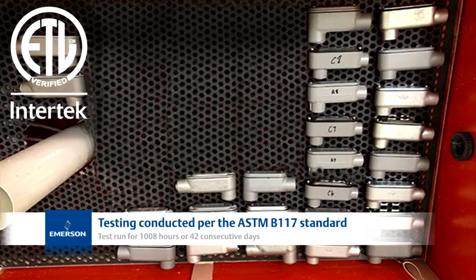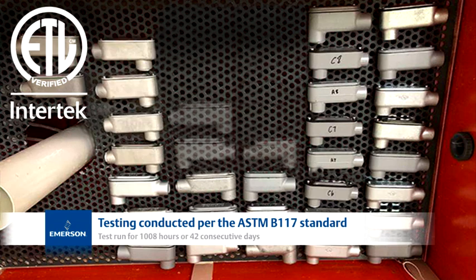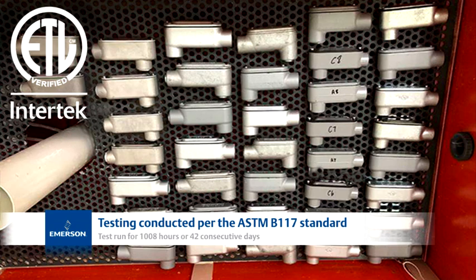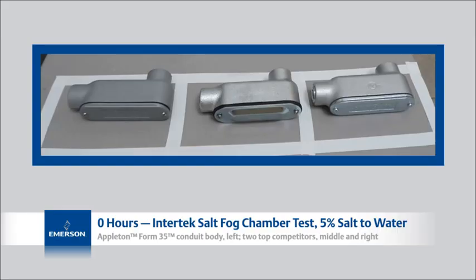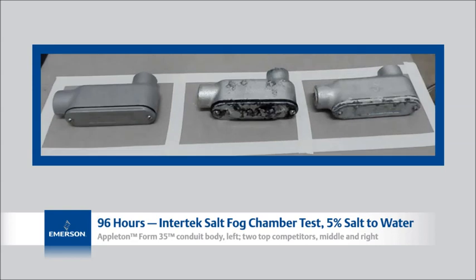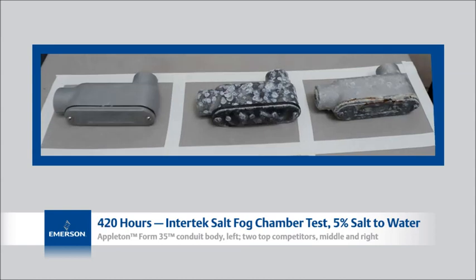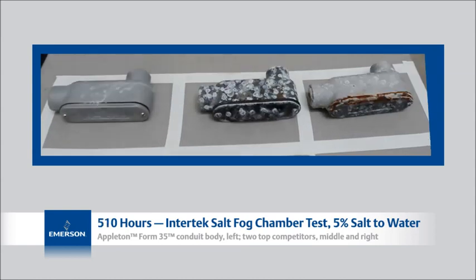Samples were placed inside Intertek's salt fog chamber, filled with a highly corrosive 5% salt-to-water ratio for 42 days. This video shows the two non-Emerson samples began to corrode in the first 24 hours. In contrast, the Appleton Form 35 conduit body looks almost good as new, even after 42 days.